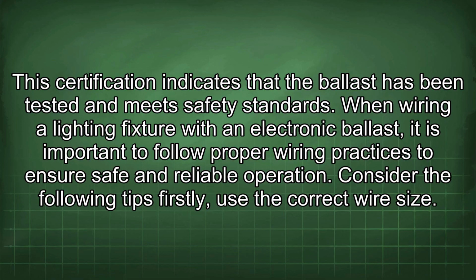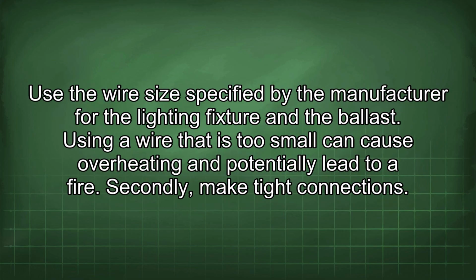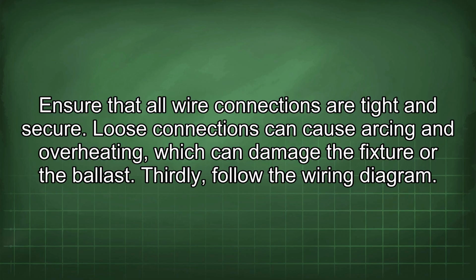Firstly, use the correct wire size. Use the wire size specified by the manufacturer for the lighting fixture and the ballast. Using a wire that is too small can cause overheating and potentially lead to a fire. Secondly, make tight connections. Ensure that all wire connections are tight and secure. Loose connections can cause arcing and overheating, which can damage the fixture or the ballast.